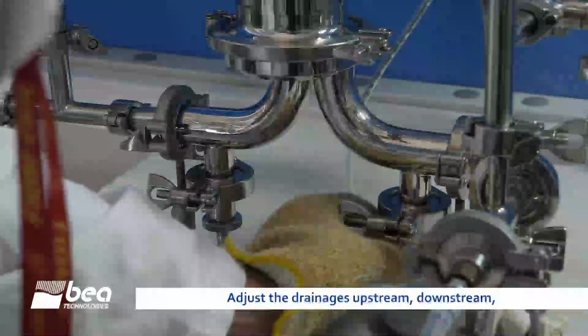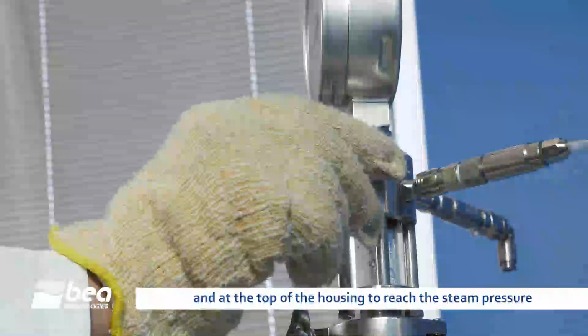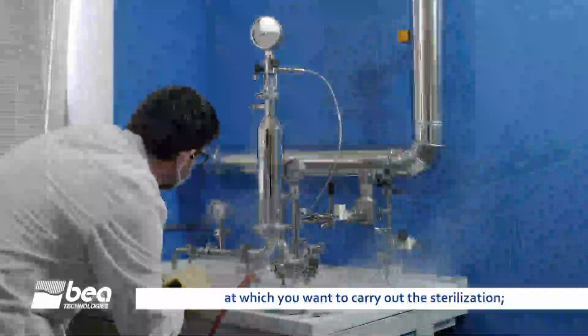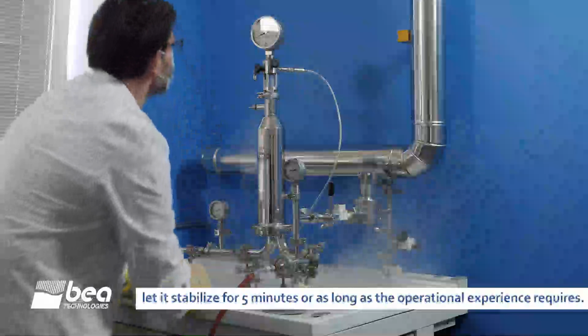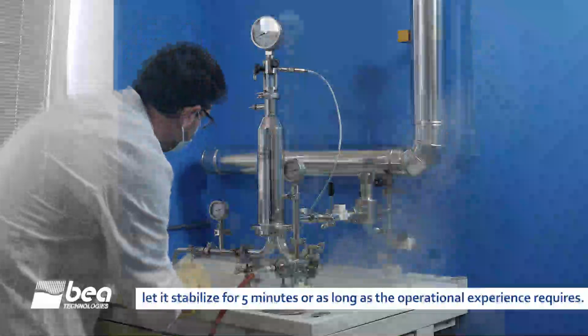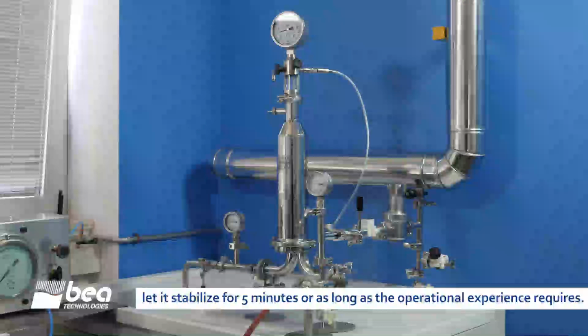Adjust the drainages upstream, downstream, and at the top of the housing to reach the steam pressure at which you want to carry out the sterilization. Let it stabilize for 5 minutes, or as long as the operational experience requires.